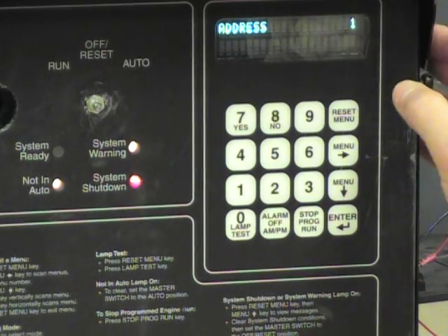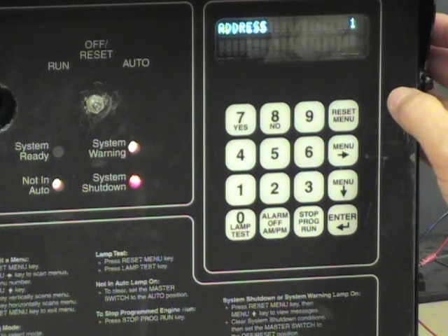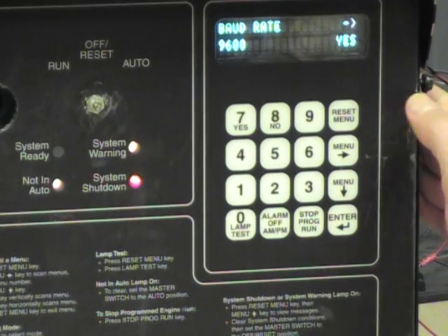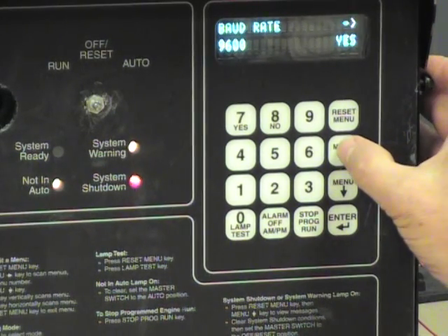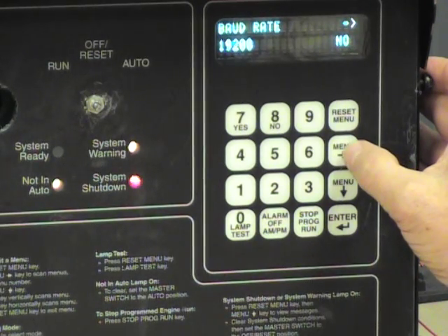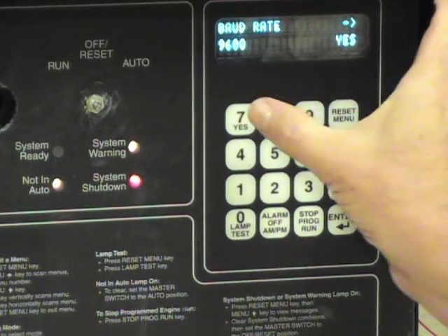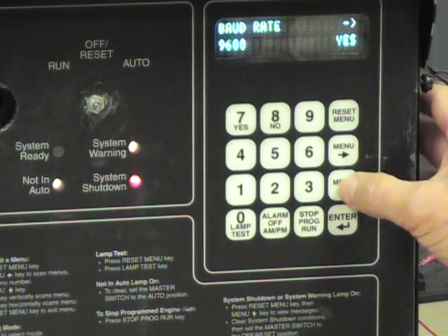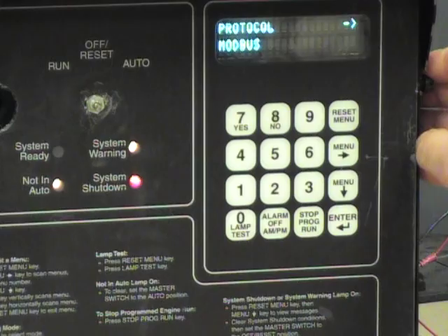We go down one more time. The Modbus unit ID, or the address, is 1 — that is the default, and we will leave it there. Down again, we come to baud rate. There are only two baud rate options: 9600 and 19200. We are going to choose 9600, so select it and press yes to make that change. Now we go down the menu one more time and we are done with that configuration.